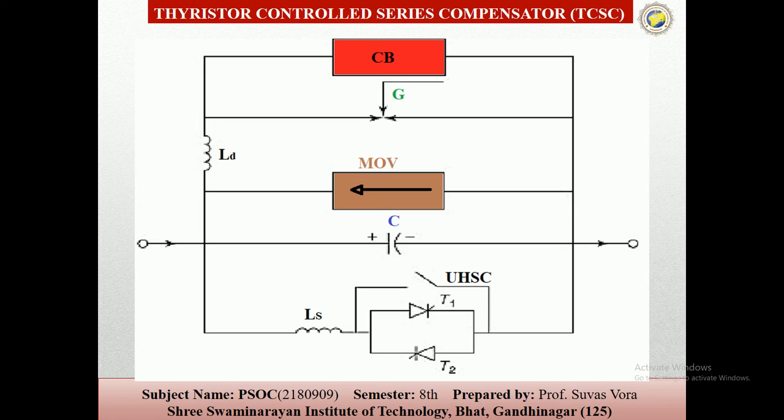So in the operation of this system, the thyristor controlled system acts as a series controlled capacitor reactance, which gives continuous control of the power and an increase in the voltage across the fixed capacitors. By varying the firing angle of the thyristor, we can control the voltage with the variations of the series capacitance reactance value.